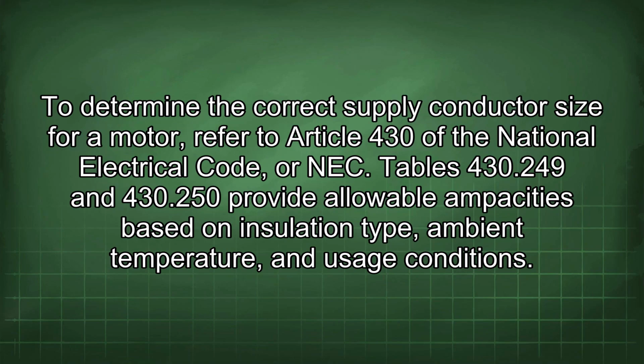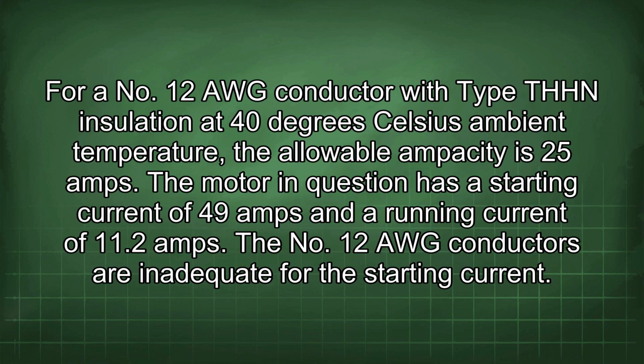To determine the correct supply conductor size for a motor, refer to Article 430 of the National Electrical Code, or NEC. Tables 430.249 and 430.250 provide allowable ampacities based on insulation type, ambient temperature, and usage conditions. For a 12 AWG conductor with type THHN insulation at 40 degrees Celsius ambient temperature, the allowable ampacity is 25 amps. The motor in question has a starting current of 49 amps and a running current of 11.2 amps.